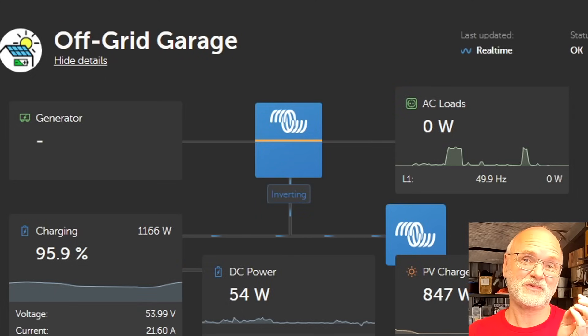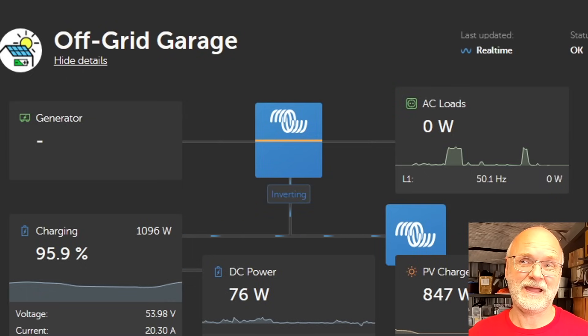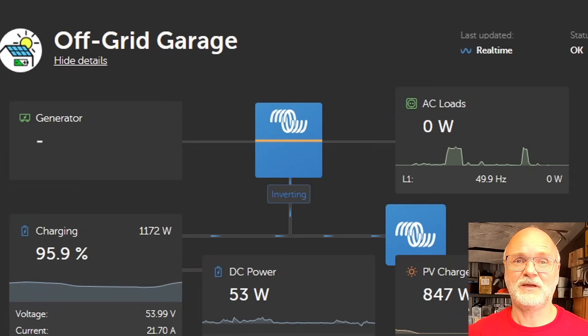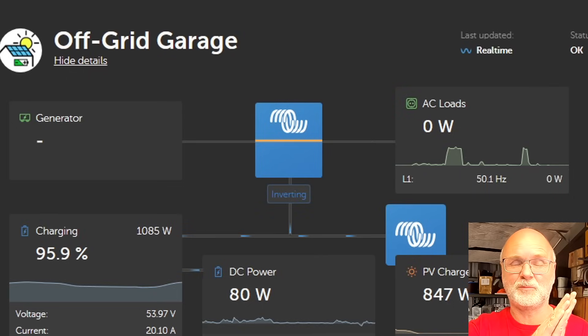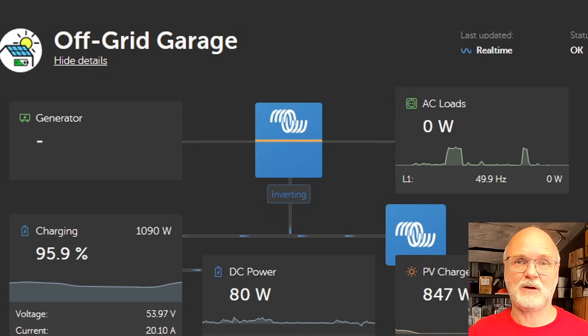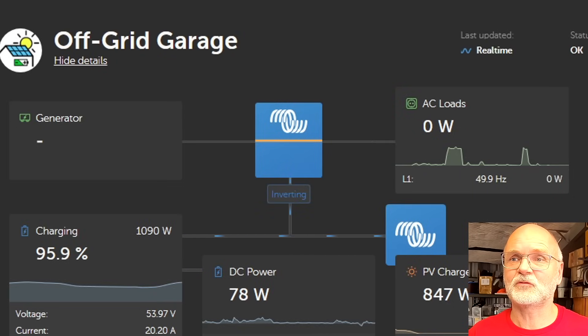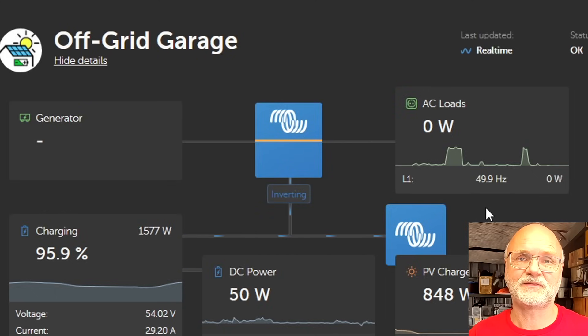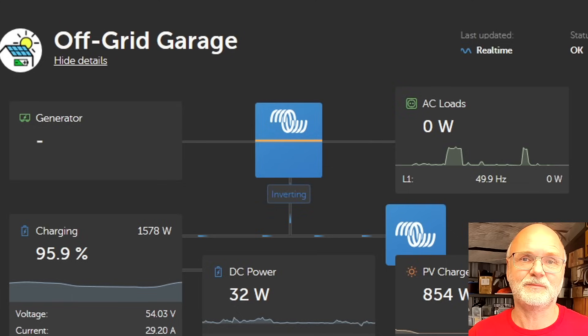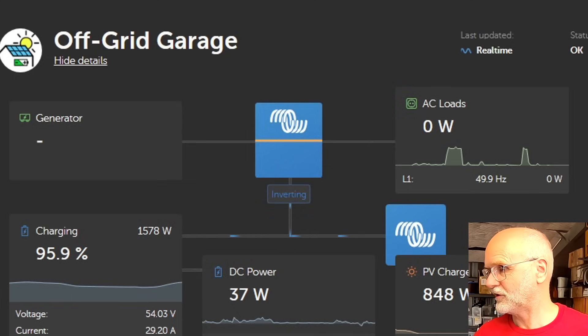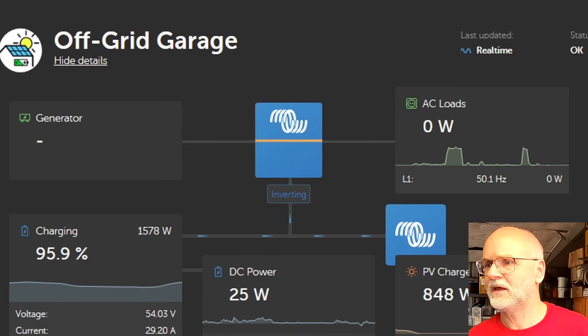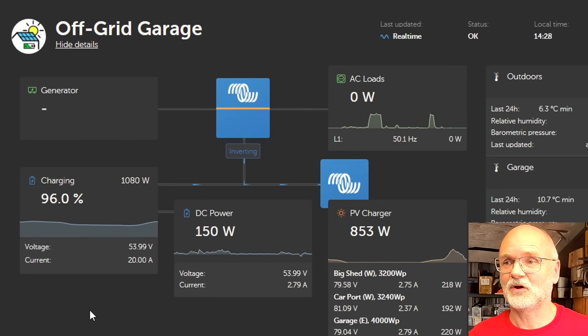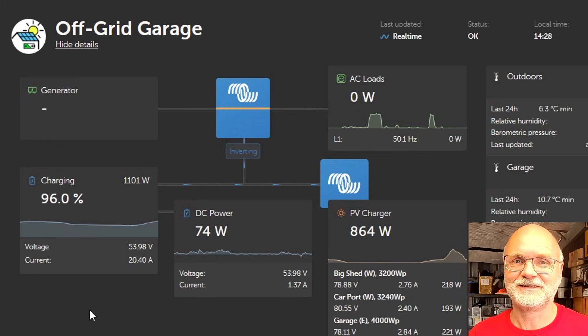I have put a Sonoff electronic switch in between the micro inverter and our multi plus. In case the micro inverter doesn't turn off, I can disconnect the Sonoff switch and the micro inverter will completely physically disconnect from our micro grid. Let's see when we hit 55.2 volts if the frequency actually increases. I'll connect another charger here to speed things up because it's already half past two and I'm not sure if we get enough sun to fully charge the battery.